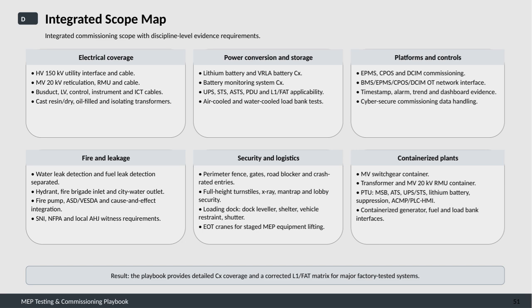resin, oil-filled, and isolating. Next, power conversion and storage covers commissioning of lithium and VRLA batteries, battery monitoring systems, uninterruptible power supplies, static and automatic transfer switches, power distribution units, and load bank tests for both air and water-cooled systems. Under platforms and controls, the focus is on verification of EPMS, CPOS, and DCIM systems, along with their operational technology network interfaces. This includes evidence generation for timestamps, alarms, trends, dashboards, and ensuring cybersecure handling of commissioning data.